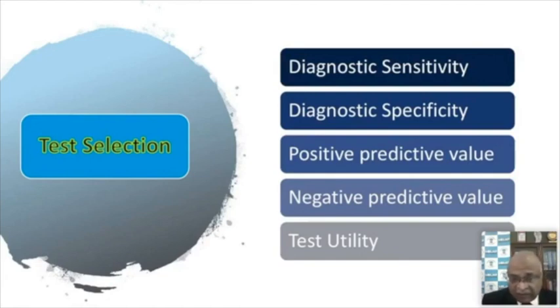Our requirement may be, it should be a 5-part differential. Suppose a hematology analyzer, it shall have autoloader, then precision for hemoglobin, RBC, platelet shall not be, say, more than 3%. For hemoglobin, linearity should be up to 25 gram per dl. All these things are our desire. Now we have to see what company people they are providing us. They may come to us with their specification.